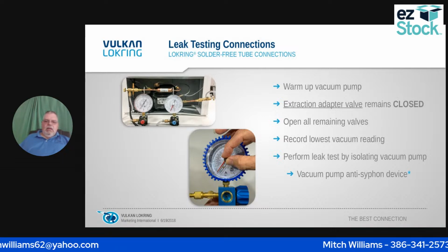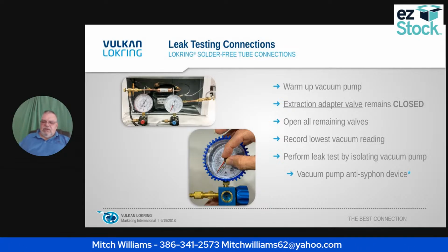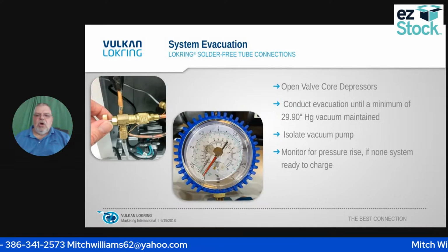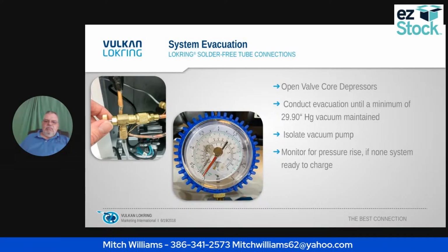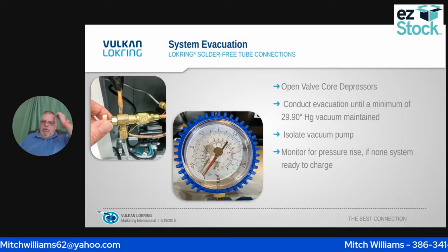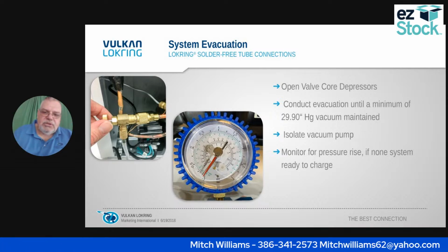So we're going to perform a leak check by isolating the vacuum pump and then the vacuum pump anti-siphon device. Once I do that, I'm going to open the valve core depressors. I'm going to conduct the evacuation until a minimum of 29.9 inHg of vacuum is maintained. Isolate the vacuum pump. Monitor for a pressure rise. If none, the system is ready to charge.